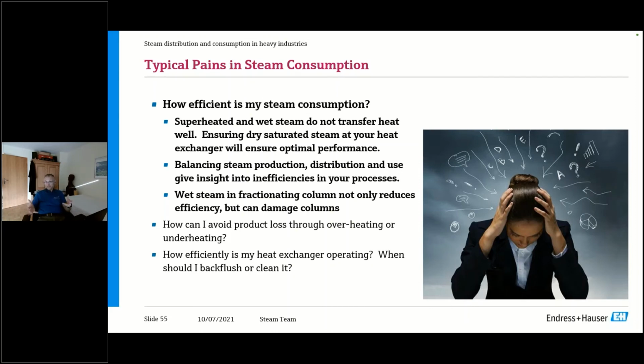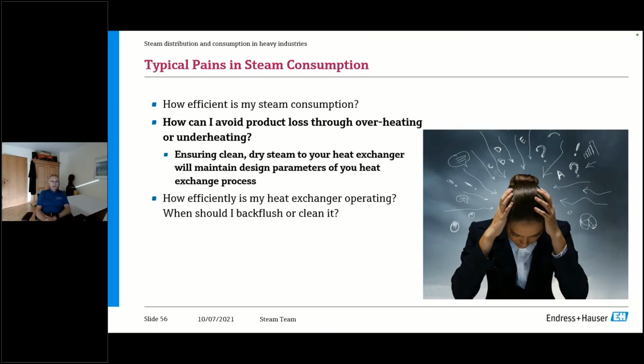And balancing the steam production and distribution gives you insights into the inefficiencies of your process once you know the dryness fraction and the degrees of superheat. Wet steam in fractionating columns not only reduces efficiency, but it can also damage columns because of water hammer, obviously. So this is very important to know. How can you avoid product loss through overheating or underheating? Exactly by knowing the right measurements, so knowing the right degrees of superheat and the dryness fraction of your steam. Ensuring clean, dry steam to your heat exchanger, you make sure that you have optimum heat exchange.